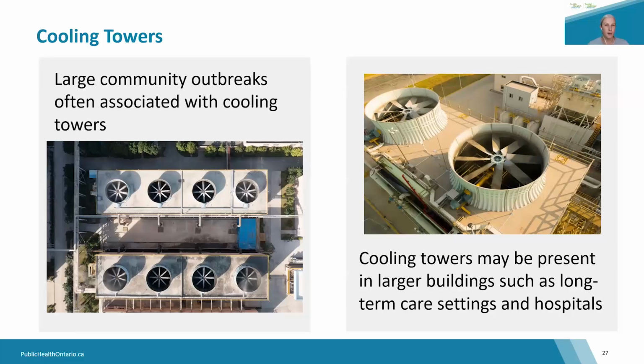If Legionella has had the opportunity to enter a cooling tower system through the environment, an inadequately maintained system can provide an environment that's favorable for the growth of Legionella. And this includes warm water temperatures and sometimes minimal to no chemical disinfection. The fans that are in the cooling towers that you can see in the images here can then spread the bacteria by aerosols or droplets of water in the air. And the aerosols can remain suspended in air for prolonged periods of time and can travel considerable distances depending on the weather and wind patterns at the time.